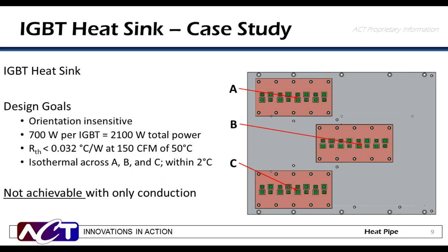Let's take a look at a case study. This is a heat sink designed to cool three IGBT modules. The design goals are: it needs to operate insensitive to orientation, it needs to effectively dissipate 700 watts from each module, totaling 2,100 watts total. There was a goal for thermal resistance to be lower than a certain value at 150 CFM airflow at 50°C. And device case temperatures at the attachment points A, B, and C need to be isothermal to within 2°C.